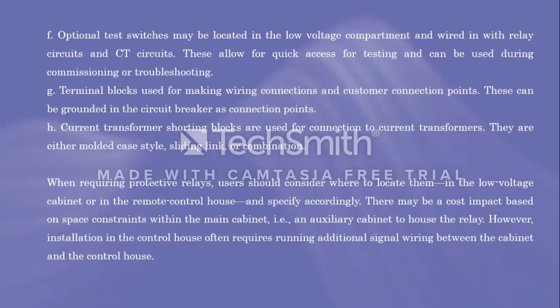When wiring protective relays, users should consider where to locate them: in the low voltage cabinet or in the remote control house, and specify accordingly. There may be a cost impact based on space constraints within the main cabinet. Example, an auxiliary cabinet to house the relay. However, installation in the control house often requires running additional signal wiring between the cabinet and the control house.